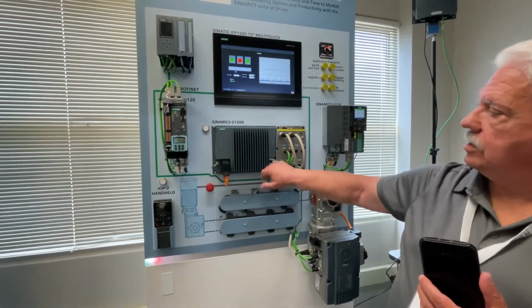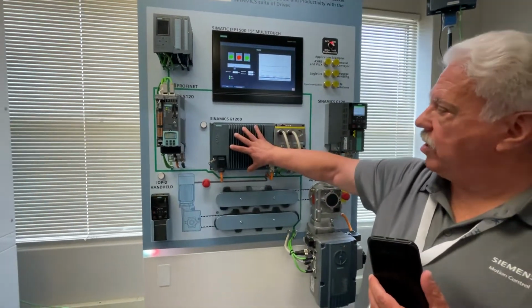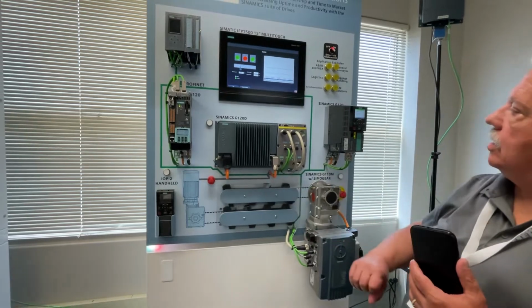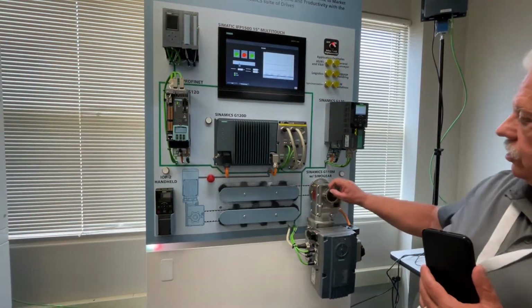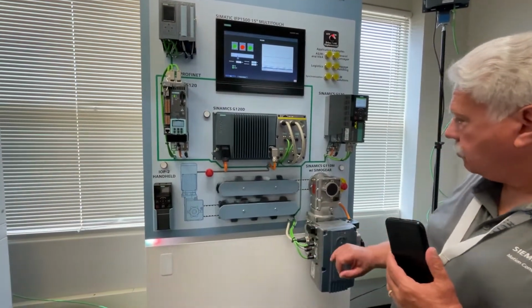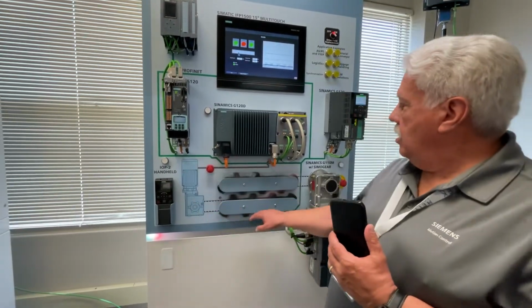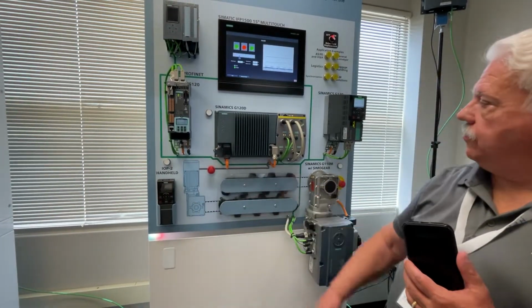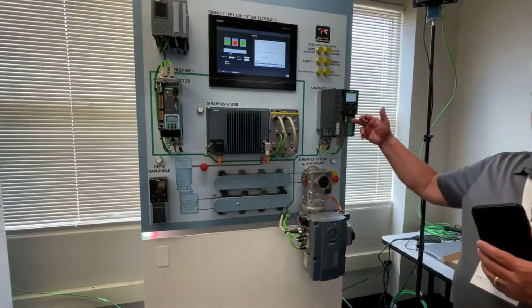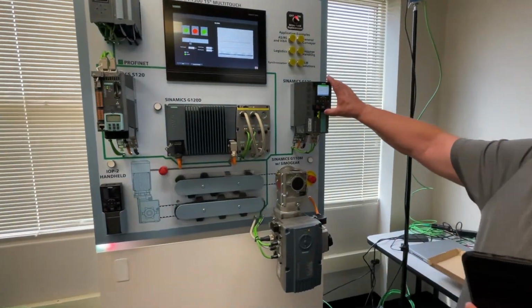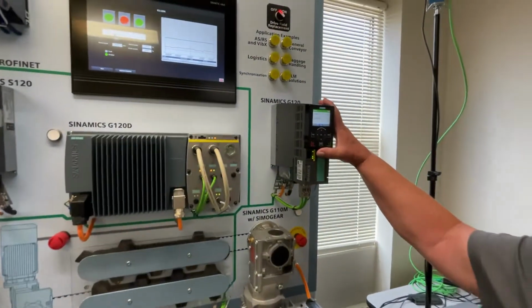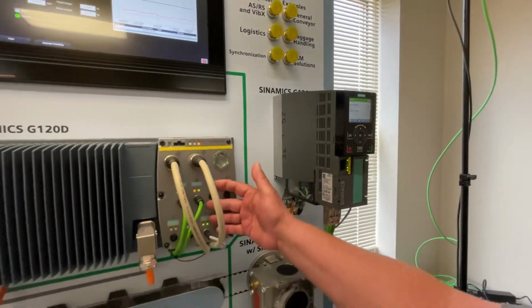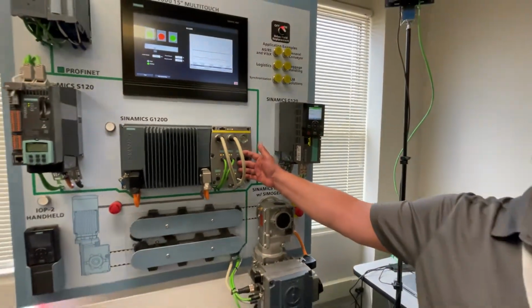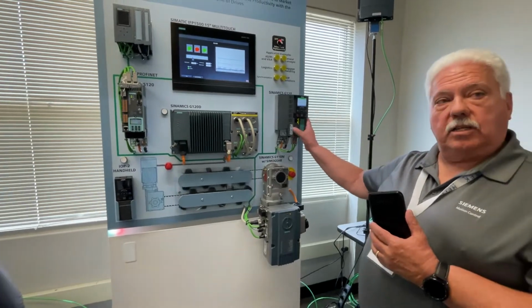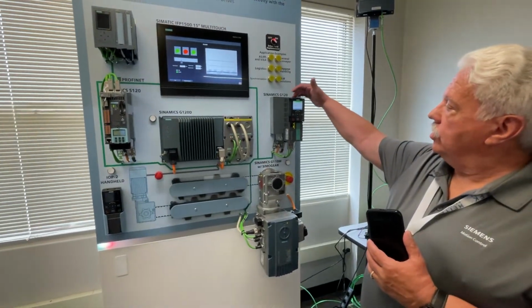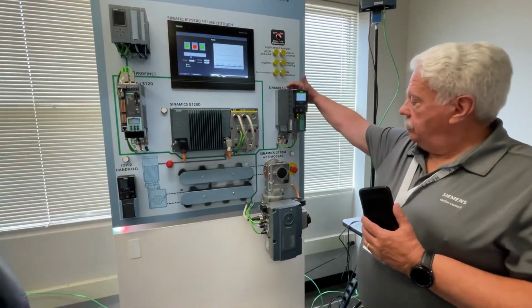Quick disconnects. These go up to 10 horsepower. There's no moving parts, as you can see, no fans. This particular one is actually driving a gear motor behind the wall that's running this conveyor. We have a modular G120 drive. This drive is designed to be mounted inside a cabinet, whereas again, this drive would be mounted out on the frame of the conveyor. Same basic internals. We have a separate control unit, and we have a power module.